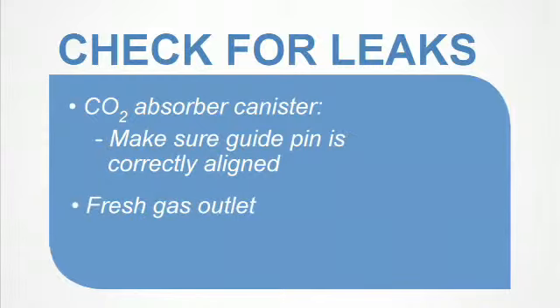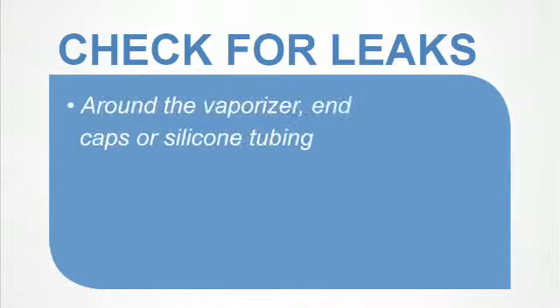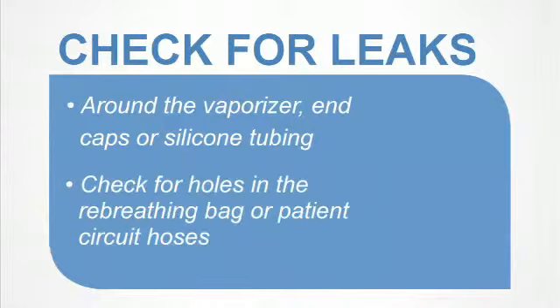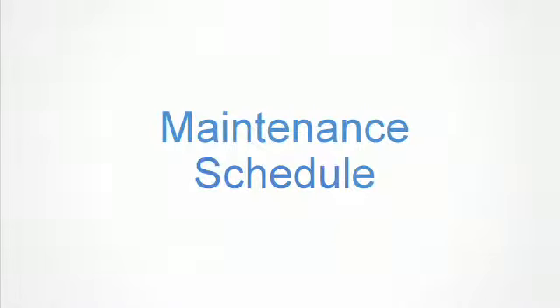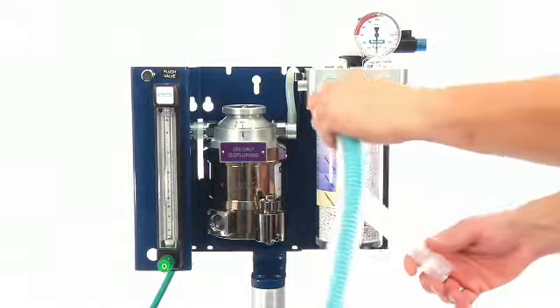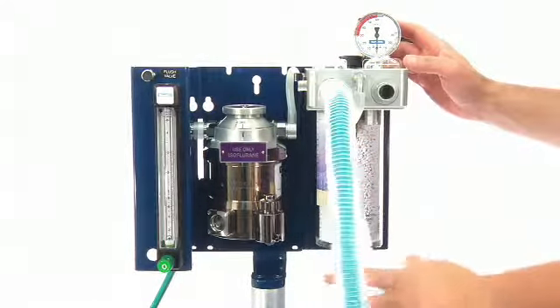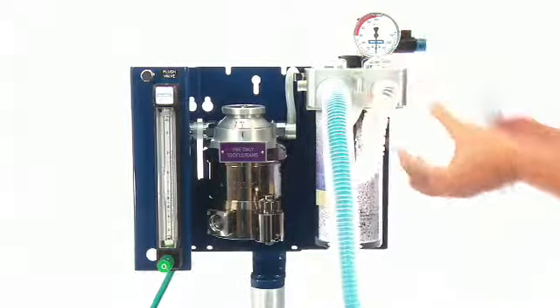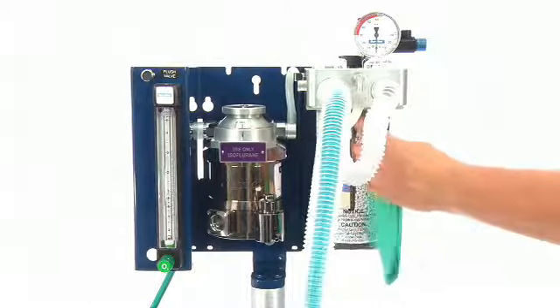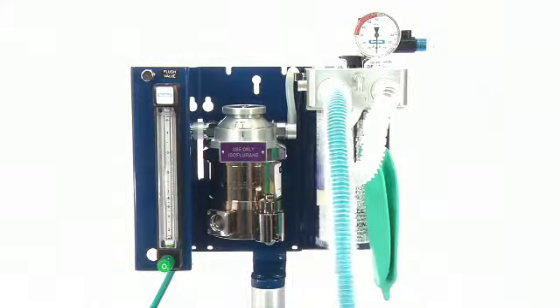Fresh gas outlet. Pop-off or relief valve. Around the vaporizer, end caps or silicone tubing. Check for holes in the rebreathing bag or patient circuit hoses. Maintenance schedule. The CDS 9000 anesthesia machine is easily maintained in the field. Preventive maintenance and daily leak tests are recommended.